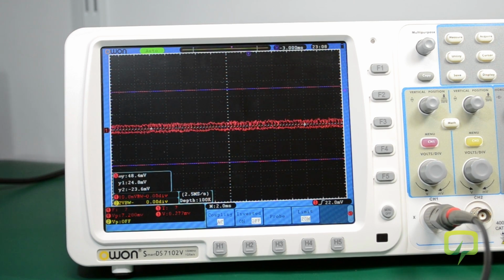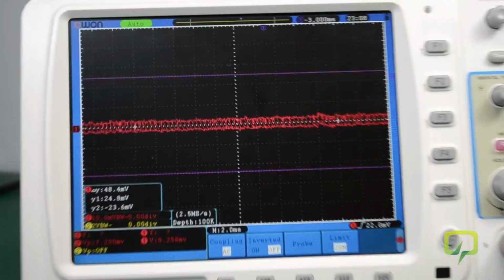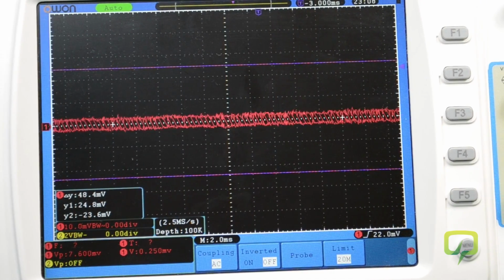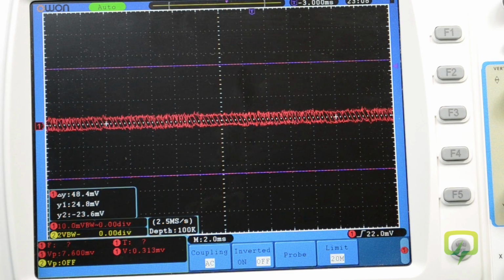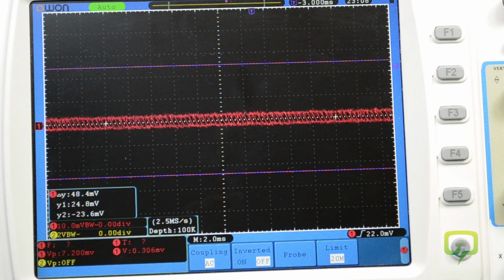The scope is obviously influenced by noise induced from the AC power line, but it's clear that without that AC power lead and the scope running just on its batteries, we're getting a noise figure of 7, maximum 8 millivolts peak to peak, which is well within the spec of this power supply, which states it should be less than 30 millivolts peak to peak, and I can certainly work with 7 millivolts peak to peak noise figure. It's not exactly a low noise power supply, but you have to keep in mind that this is a switch mode power supply and not a linear one.